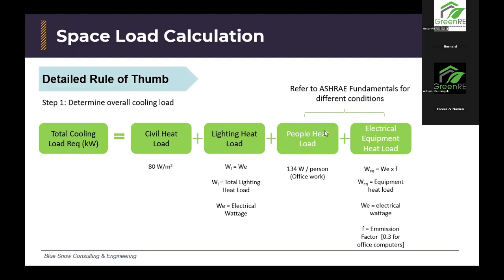Like Faris mentioned earlier, when you're using SI units, the wattage, you need to be careful what kind of wattage we're talking about, electrical or heat. Then we have the other loads, like people heat load. In this case, it is 134 watts per person for office work. And then the last one is the electrical equipment load. This will also be determined, like say your computer is 100 watts. A computer does not function the same way as a light bulb would. So there's something called an emission factor. These are based on the standards. For example, if you look up the fundamentals handbook, you'll be able to find the emission factor for a computer, what it may be.